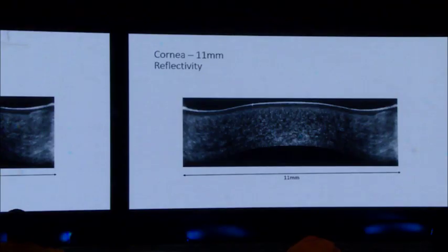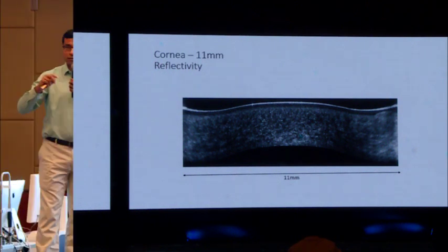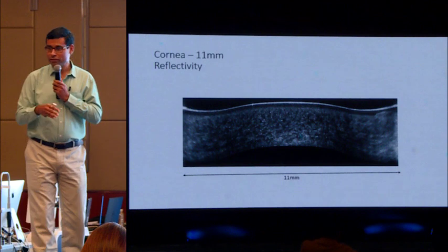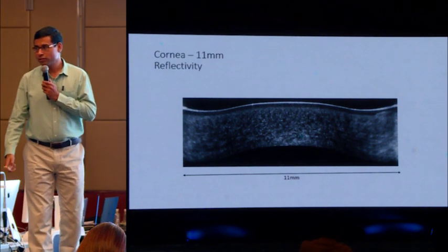It's a very thin layer, so we are going down to 1.4, and going down below has registration issues, and depends on how well the patient is able to fixate. So for doing, let's say, topography and layer thickness, we want to go faster. For doing collagen mapping, we have to go slower. So there are different scan protocols that we have implemented here.